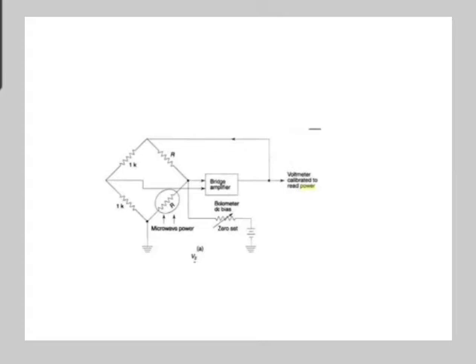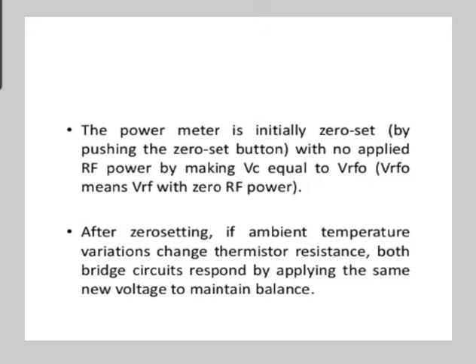They are based on the conversion of microwave into thermal energy, and a device which is known as a bolometer is employed by the power meter, and the output of the bolometer is processed to represent the power level on a calibrated scale. Now the temperature of the bolometer rises when the microwave power is incident on it, and because of this change in temperature, there is a variation in the DC resistance of the bolometer. The resistance can increase or decrease, and therefore bolometers are classified as one, positive temperature coefficient type, and the other, negative temperature coefficient type.